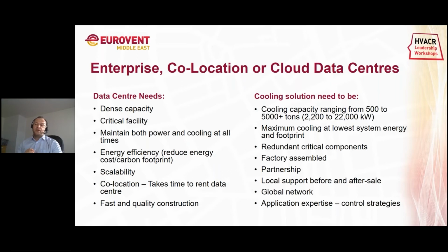As for example, co-location, initially it takes some time to rent the data center, and it can be that initially only 10% of the data center is occupied. On top of that, they want to have a fast and quality construction of the data center. So when we think of the cooling solution that meets these demands, we're looking at a cooling capacity in a range from 500 to 5,000 plus tons.